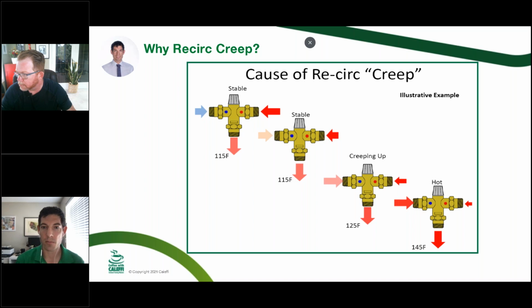And then on the bottom right, what's happening is no one's using any fixtures. So we're recirculating up to 145, and then we're only losing a couple degrees through the piping, and that's what our cold is now. So our hot is 150 or 160 or something like that, and then we're getting 143 back in as the cold. And a thermostatic mixing valve can't keep up with that unless it can close 100% off the hot. Which some of the valves do, but most of them don't.